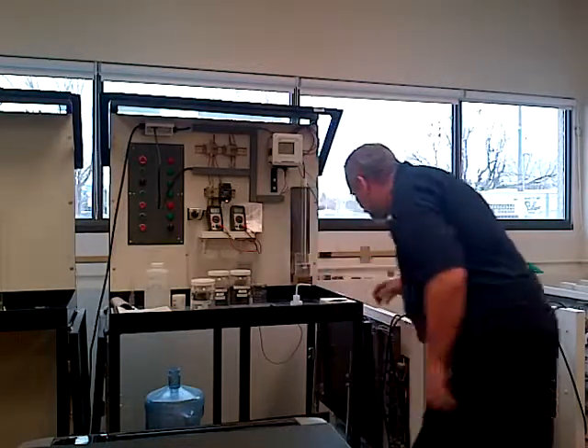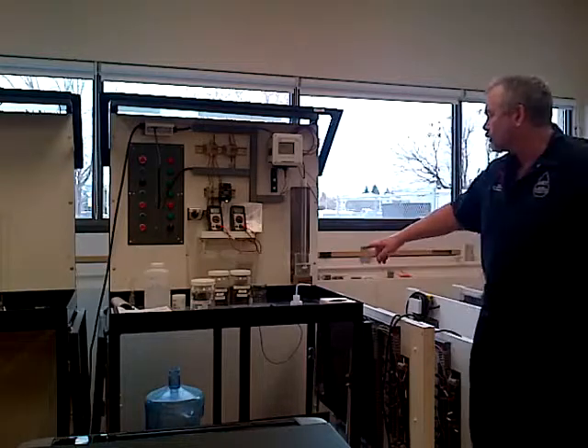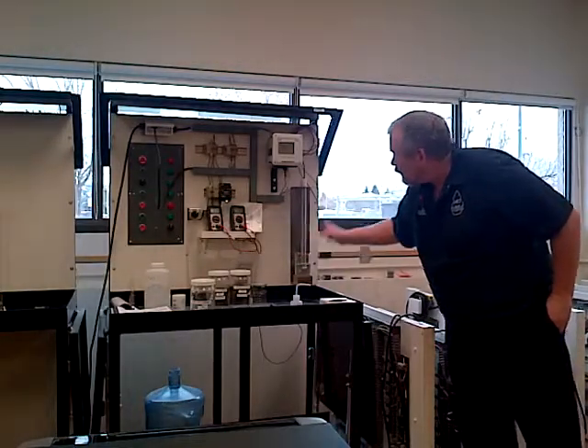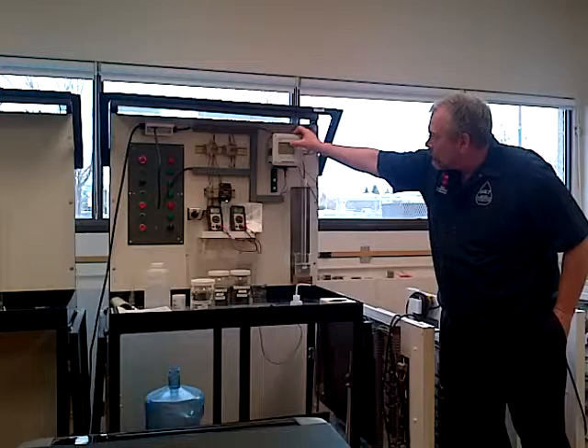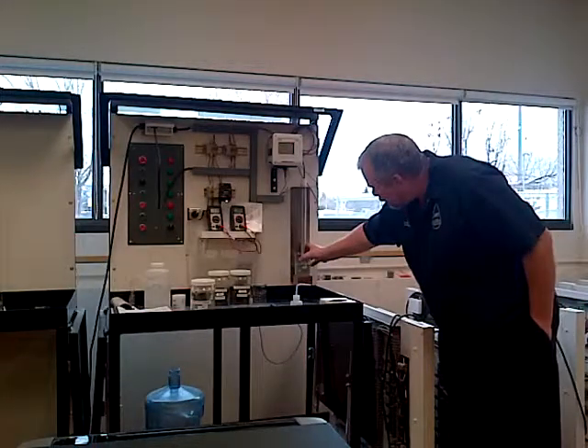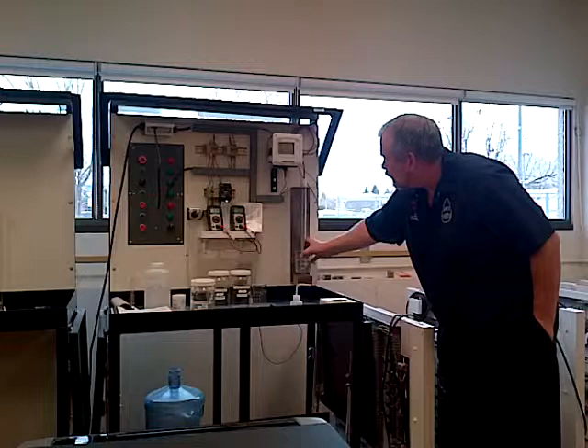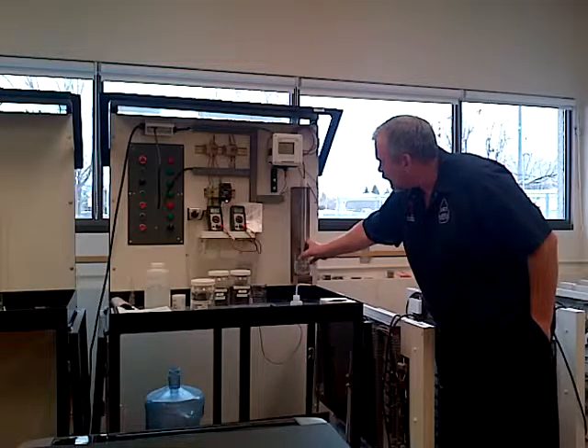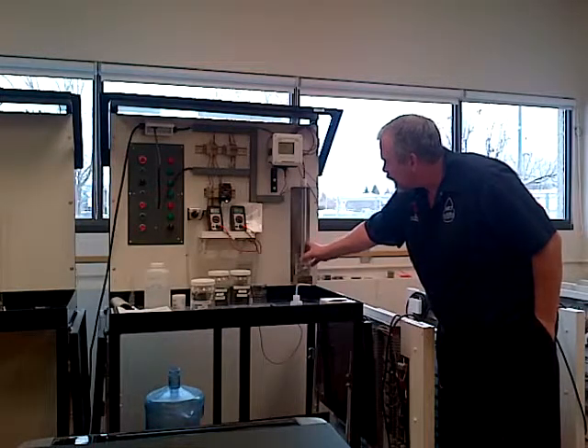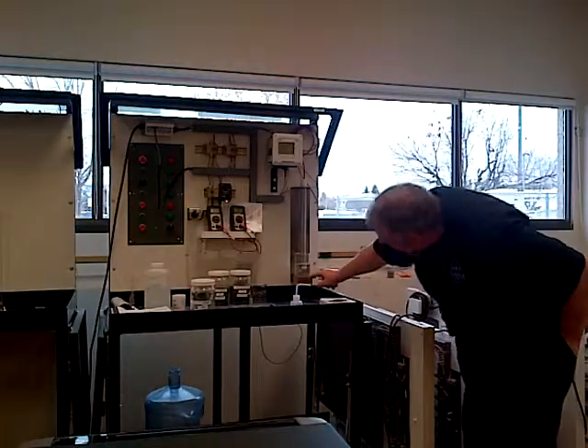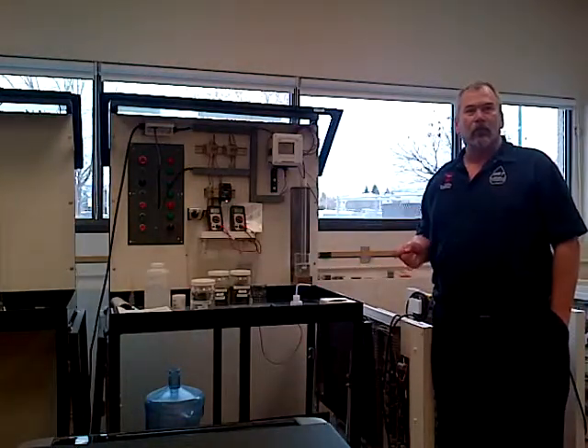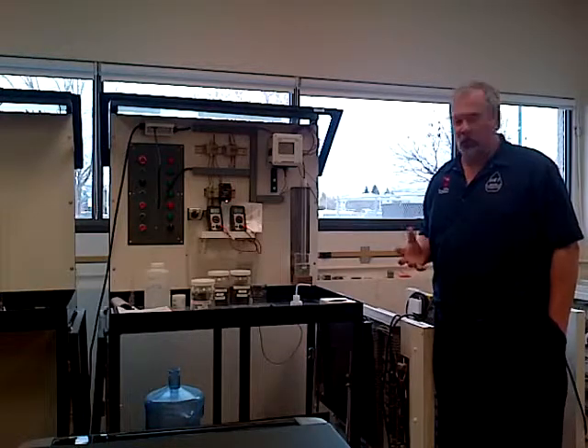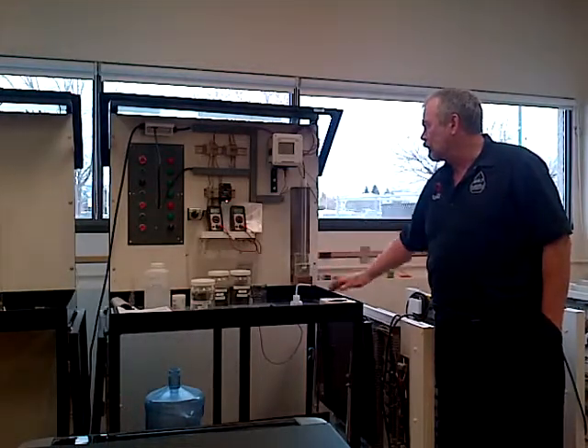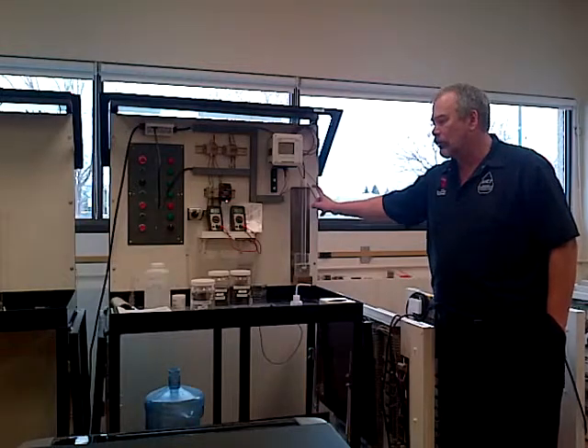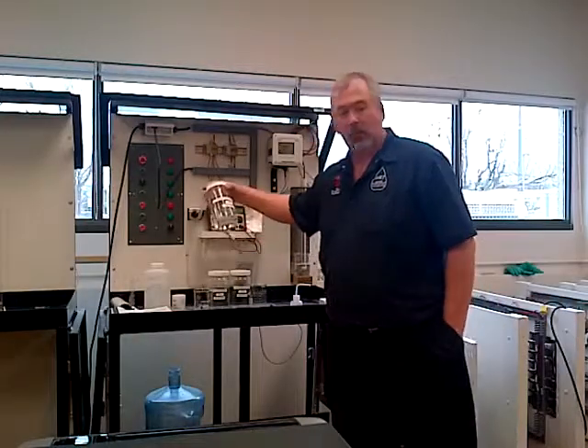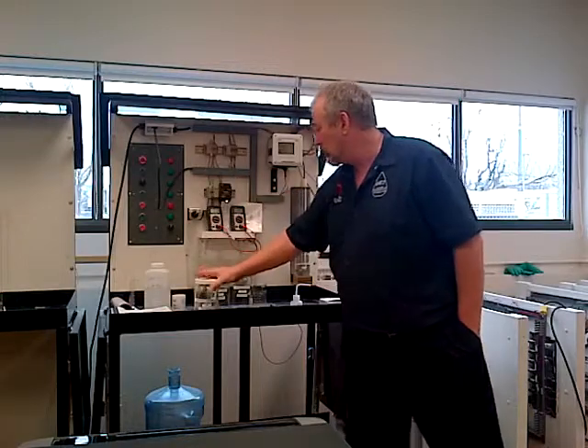Now this probe has to be totally covered, and we're just going to let it stabilize. It's at 800. That's not good. But watch what happens if I put this right to the bottom here. See it drop like crazy, or even close to the bottom, or to the sides. It gives you a false reading. You have to have about, the book says, an inch. So for us, 2.5 centimeters, these are metric, around the probe. Yeah, that 1,000 is way off. It's probably an old standard. It either needs calibration or a new standard.